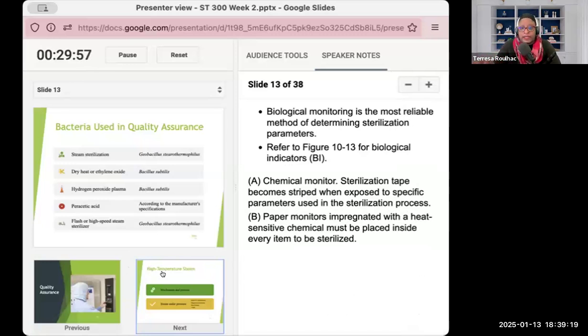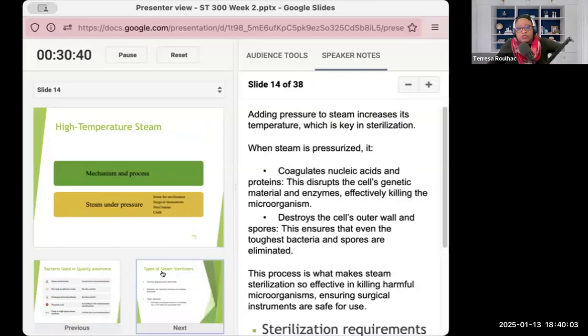Now, biological monitoring is the most reliable method of determining sterilization parameters. In the book, 1013 gives you an idea of a biological indicator, so make sure you go check that out. Chemical monitors, again, think about sterilization tape, a strip that turns colors, and paper monitors that are impregnated and heat sensitive. They're placed inside every item to be sterilized. When the instruments go in, they put that in there as well, and then they take it out to make sure that all the parameters have been met for sterilization to have taken place.